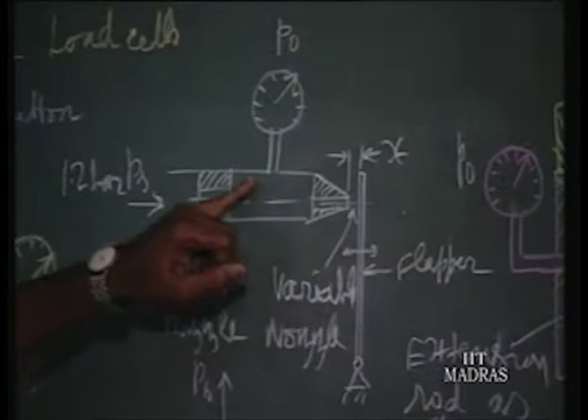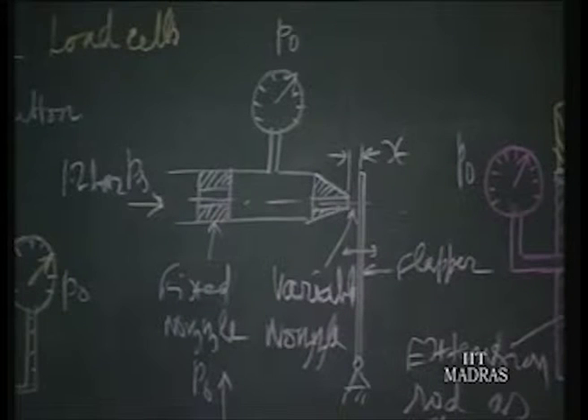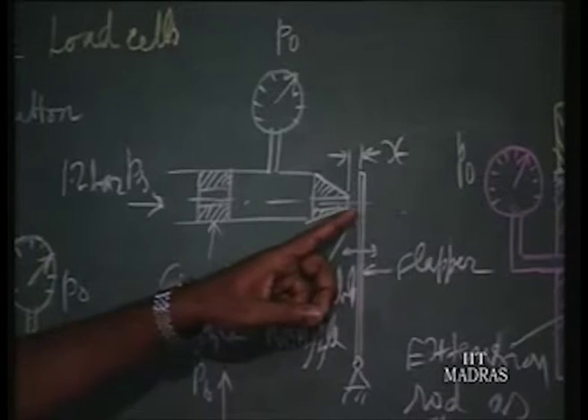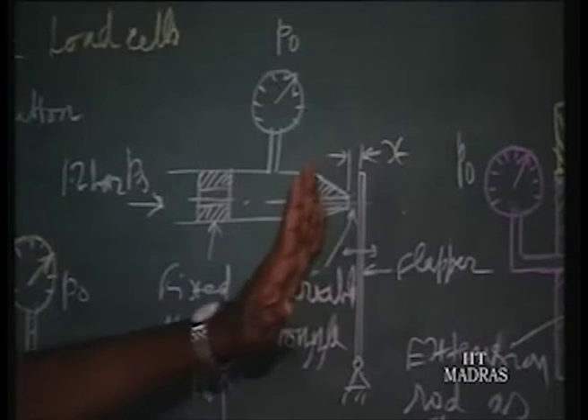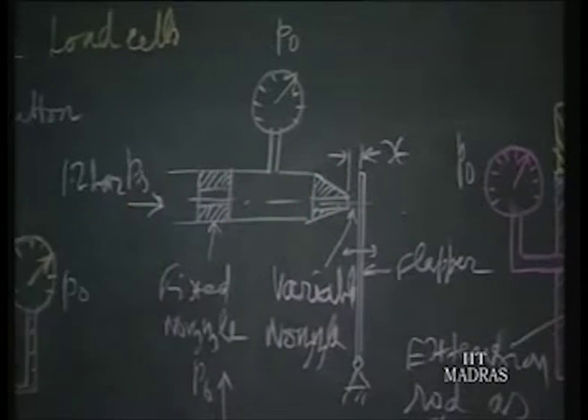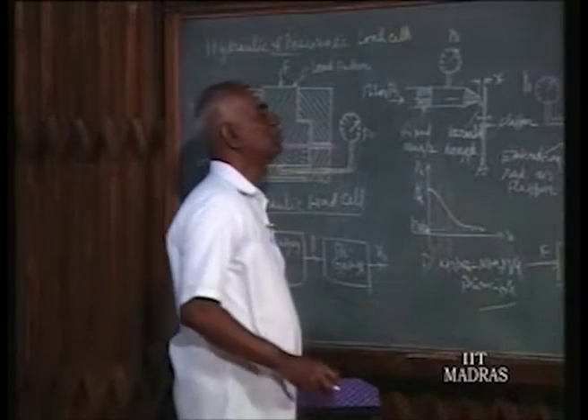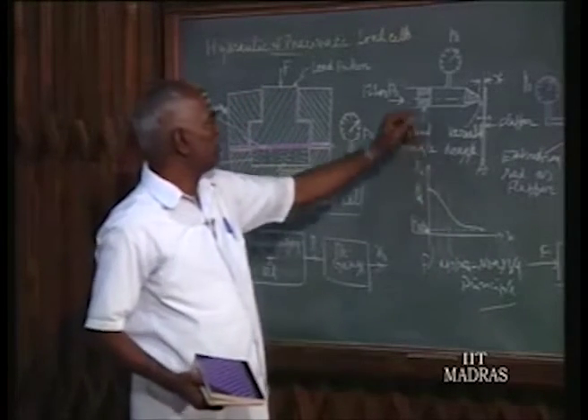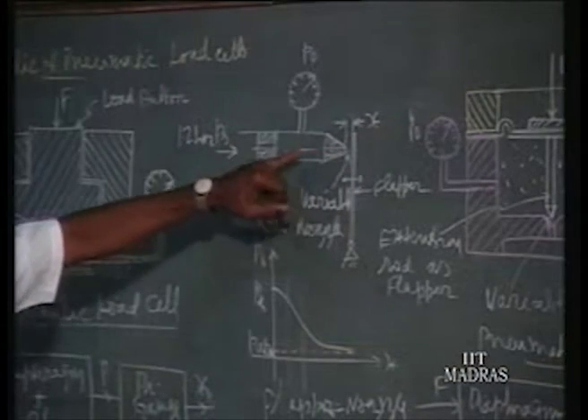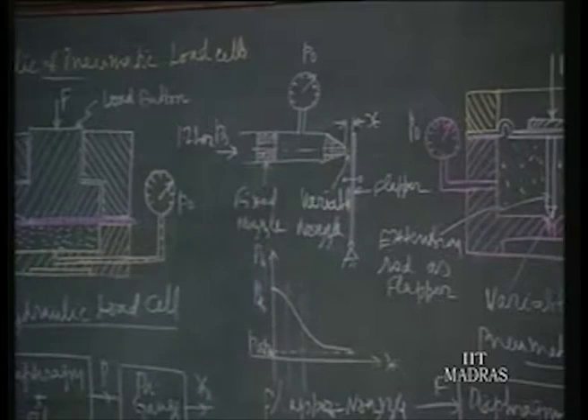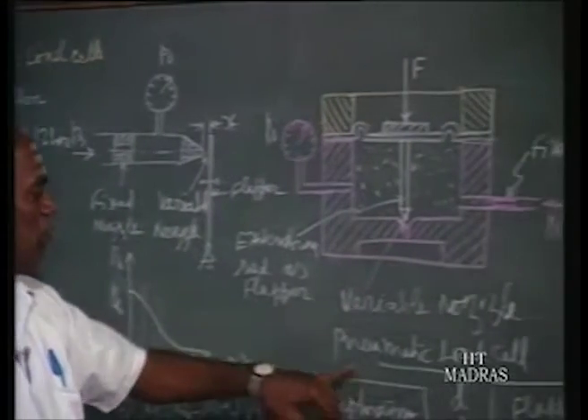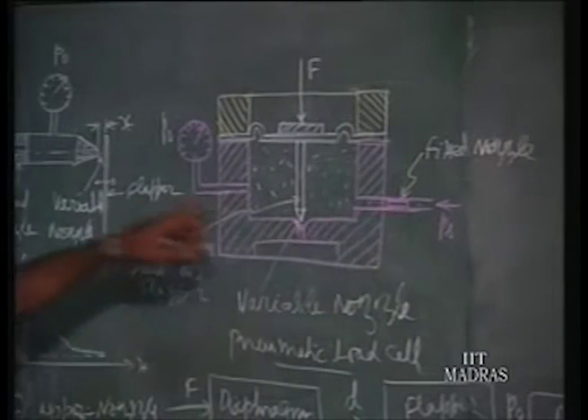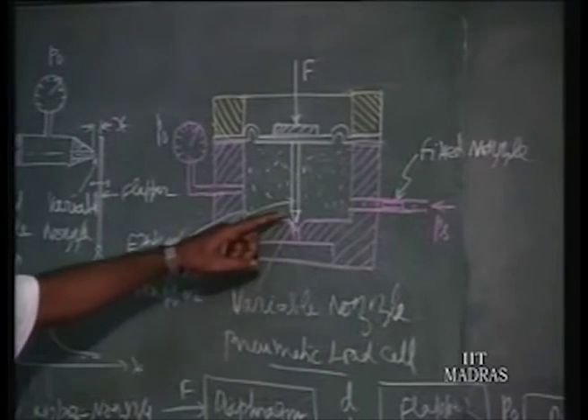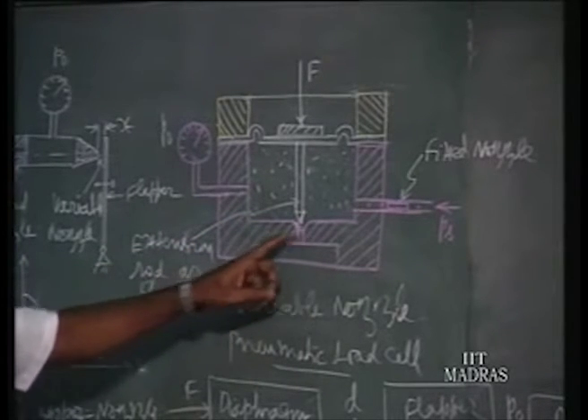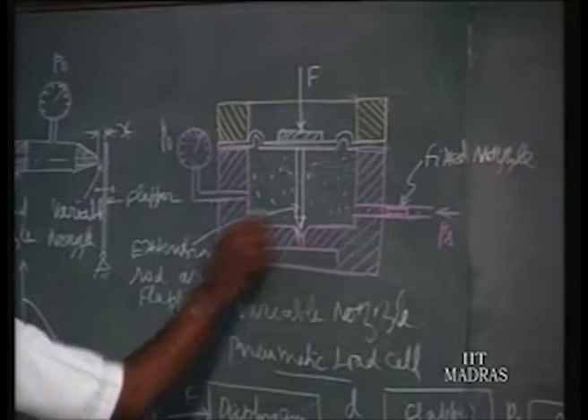So as x varies, the PO varies as per this curve. When x is equal to 0, PO is PS. That is, when the flapper fully closes, this pressure becomes the supply pressure. For any other distance x, it varies. More or less you get some range as a linear range in this instrumentation. Anyhow, this is the principle. By giving a displacement x, we convert that displacement into a pressure by the flapper nozzle principle. That is what is made use of in this pneumatic load cell. We have got a fixed nozzle similar to those fixed nozzles, and a variable nozzle between the extension rod and the bottom wall. We have this variable area.